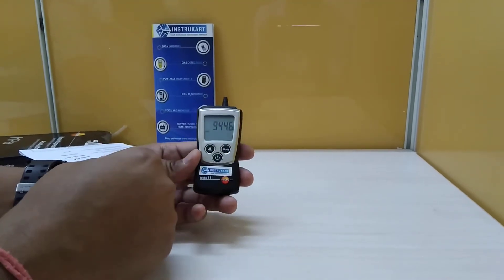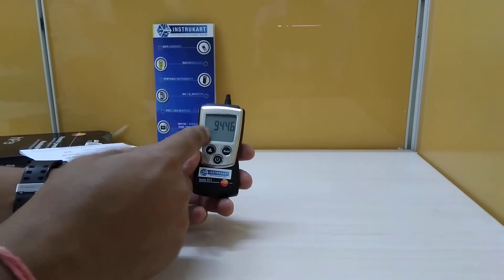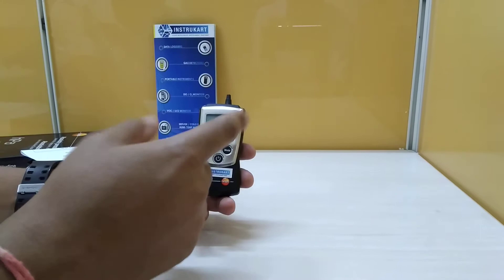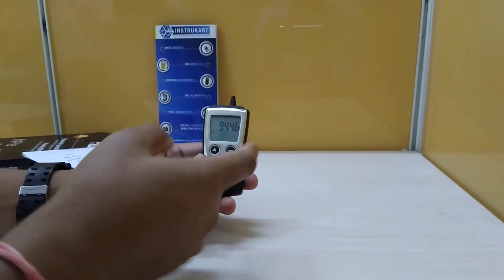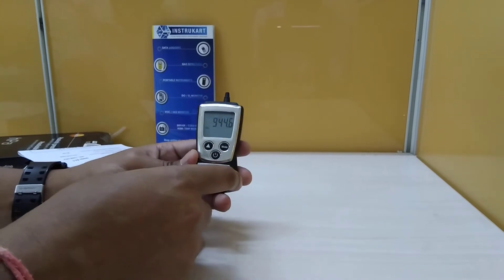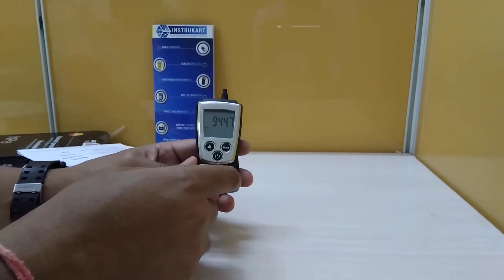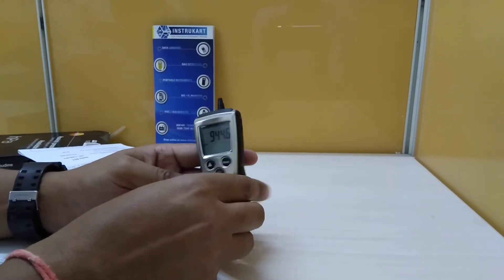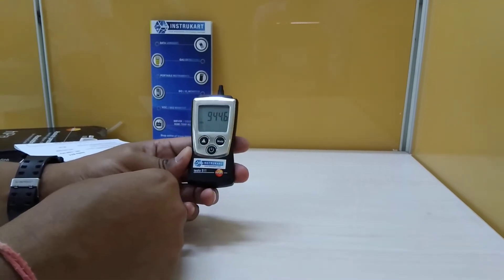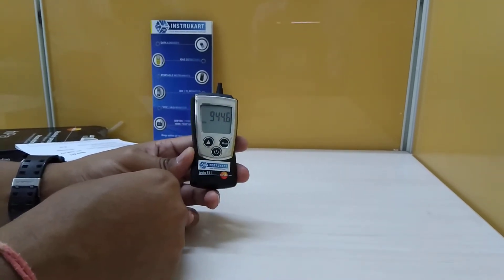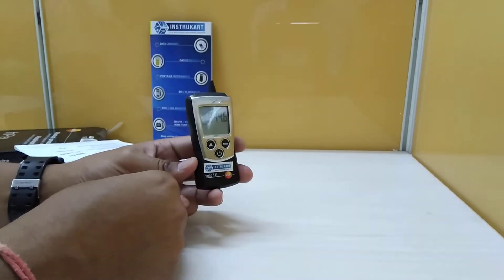This has a parameter of absolute and barometric with engineering units of Pascals, hPa, millibar, mm H2O, mm Hg, inches Hg, inches H2O, and psi. The measuring range is 300 to 1200 hPa, and the resolution is 0.1 hPa.